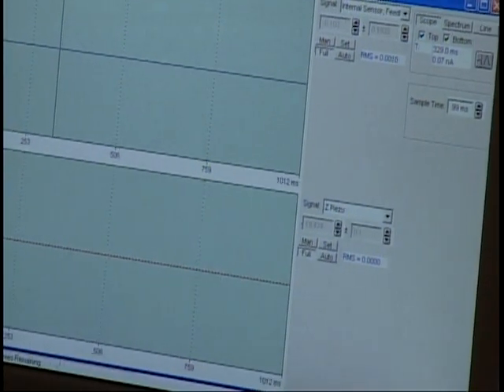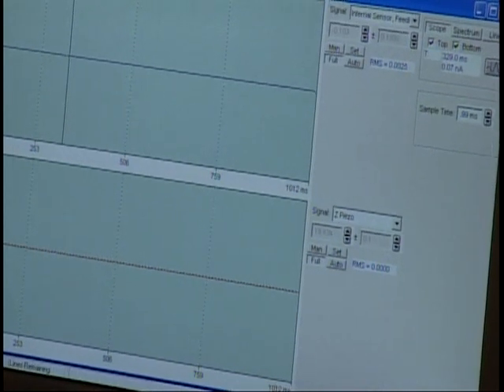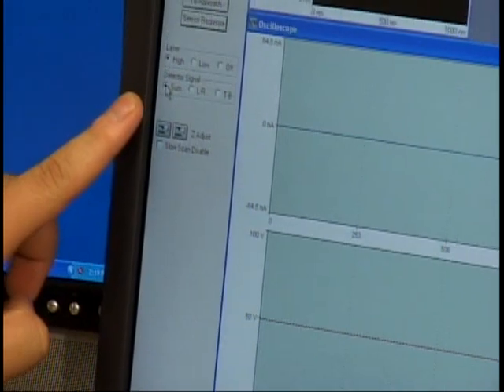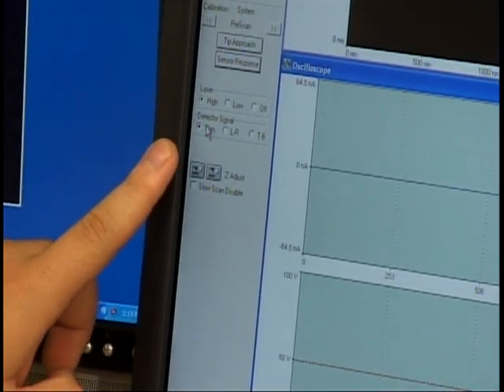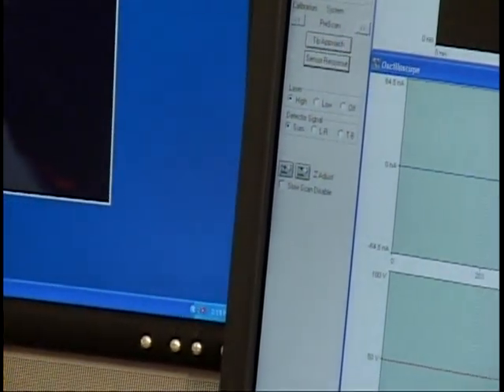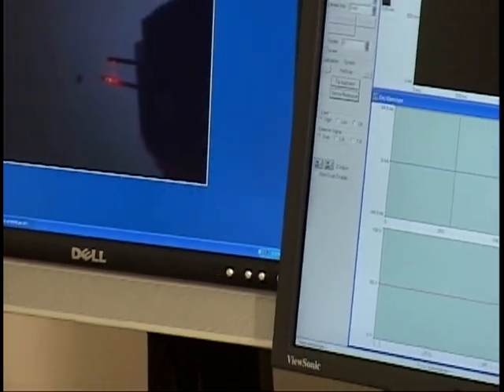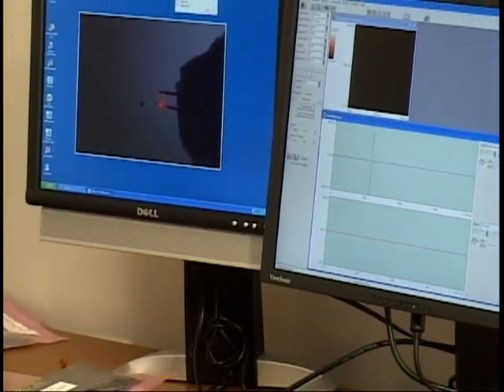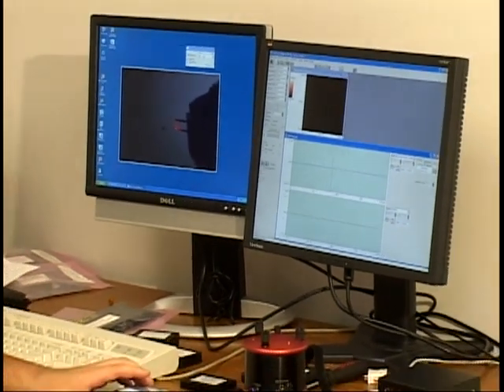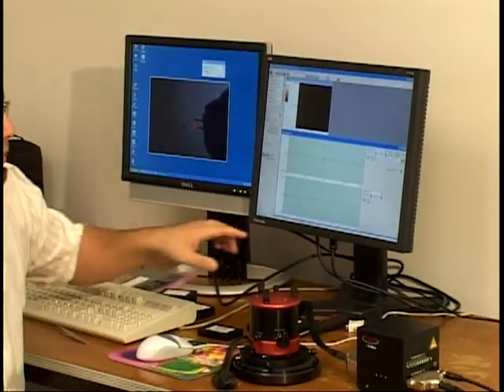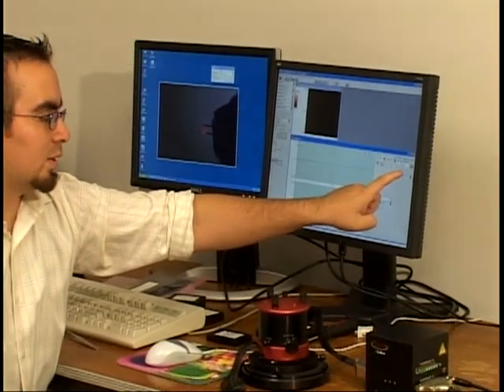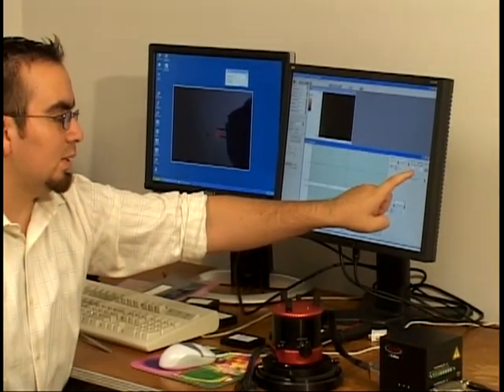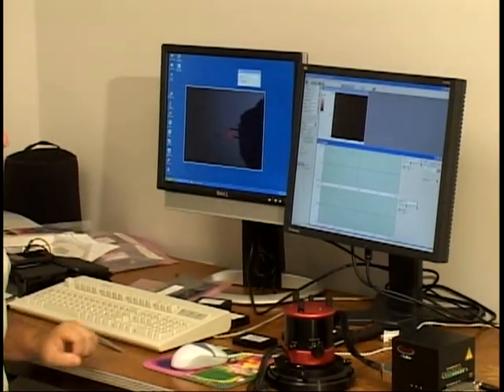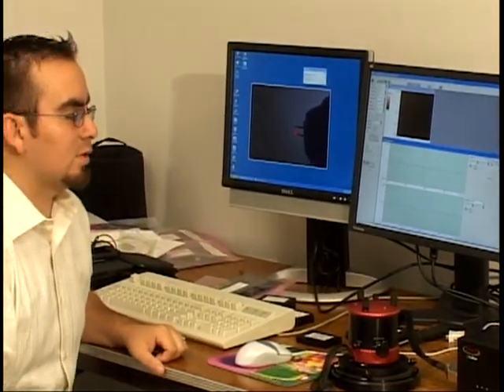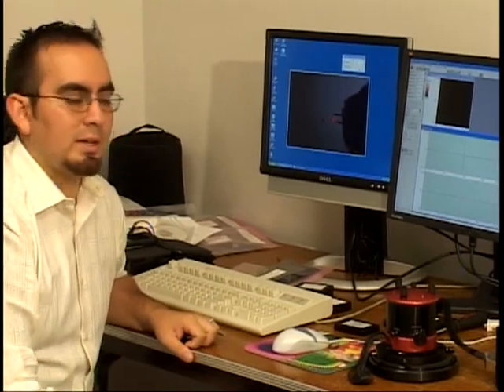So once we got the laser on the probe, we want to switch the detector signal to sum, the sum value, right here. Once we have it on sum here, on the oscilloscope, we want to left click on the oscilloscope, and you'll get this vertical line going across it. This will give us the readings on the oscilloscope. And right below where it says T, you'll see a value, we're in nanoamps. That's our sum value. Right now it's 0, so we're not aligned at all.